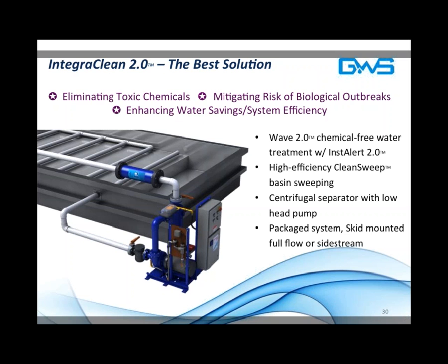However, our service partners, when they service the site, will do a field test, and they will also take a water sample test as well on every visit. And so essentially, there is no direct measure of biological within the system, but there's an indirect assurance that we have based on effective conductivity parameters and recirculation flow. I would say that the most important indicator of biological control is flow through the wave. So if we have recirculation, then we know we're effectively controlling biological growth. And we do monitor that.